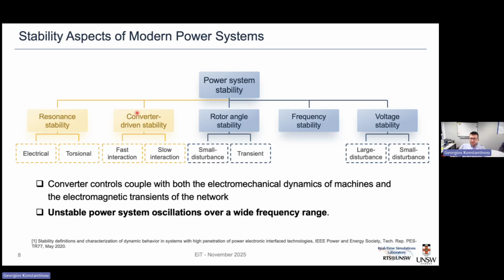So what we see here is this coupling between converter controllers and the electromechanical dynamics of the machines, but also with the electromagnetic transients of the network. So different time domains, but interactions over a much broader frequency range. This means that the instabilities we experience in the system also see this wider frequency range. Oscillations and interactions could be as low as fractions of a hertz, and as high as higher than the fundamental frequency, well into the few hundreds of hertz.